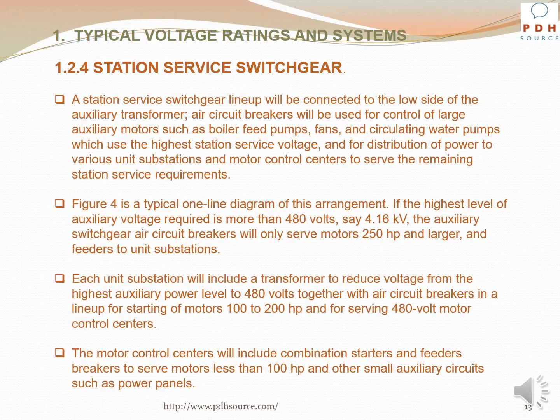A station service switchgear lineup will be connected to the low side of the auxiliary transformer. Air circuit breakers will be used for control of large auxiliary motors such as boiler feed pumps, fans, and circulating water pumps, which use the highest station service voltage, and for distribution of power to various unit substations and motor control centers to serve the remaining station service requirements. Figure 4 is a typical one-line diagram of this arrangement.